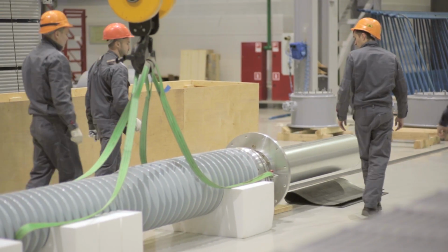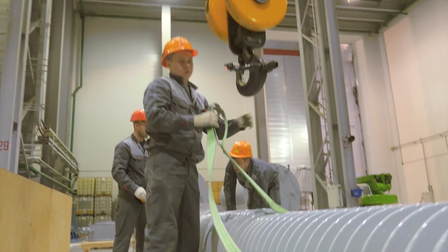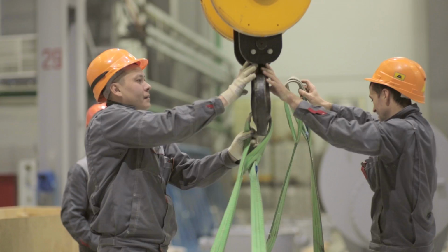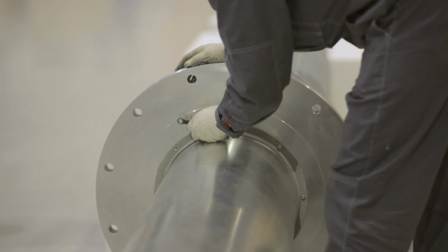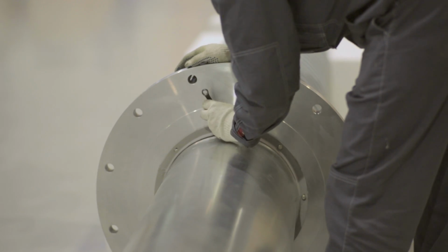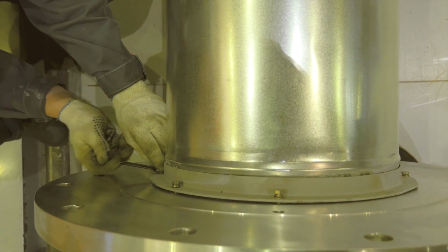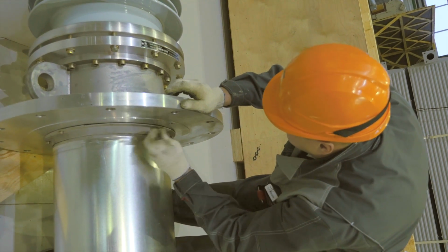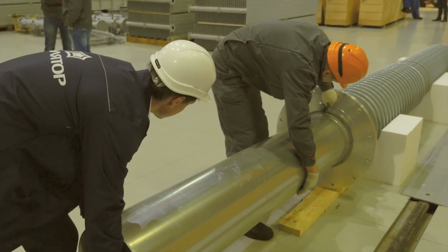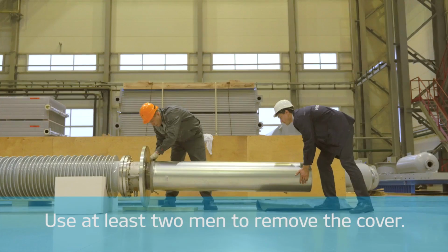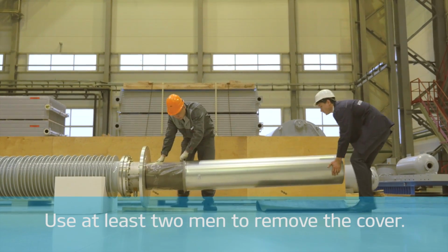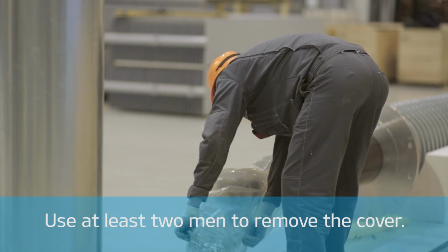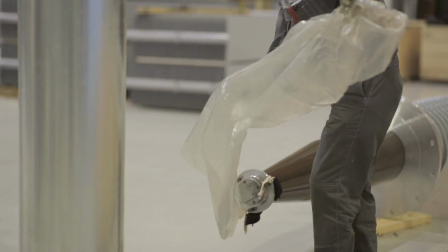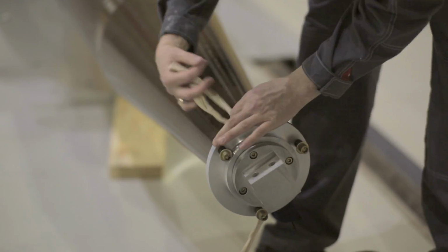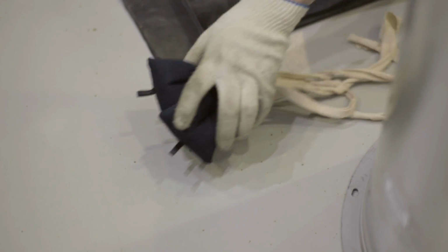packaging. Unbolt and remove the shipping cover from the bottom side of the bushing, which is attached to the central flange. The cover is used to prevent the bottom side from any mechanical damage when shipping and storing. To avoid any damage to the bottom side of the bushings, use at least 2 men to remove the cover. Also remove polyethylene cover from the bottom side and silica gel bags used for protection against humidity.